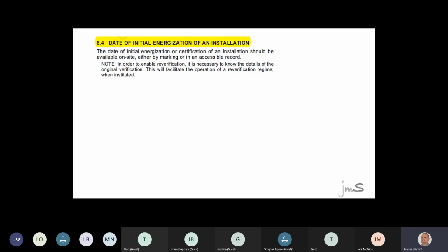Last but not least, for testing, remember to put the date in the switchboard once you tested it. It's always good because insurances will check it. Now, I'm an inspector. Do you know that inspectors must go to a database and type it in? So there's one option, I can go to the database. But guys, all entries in the database only started around about 2010. What about before all that? It's going to be very hard if the date's not in the switchboard. But there's a very clever way. And the clever way is this.